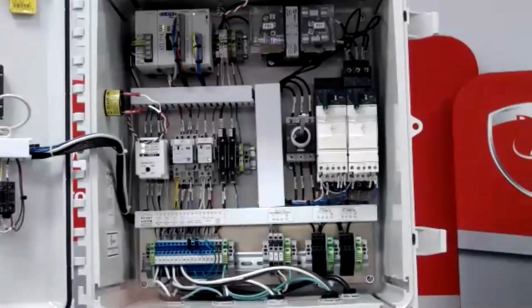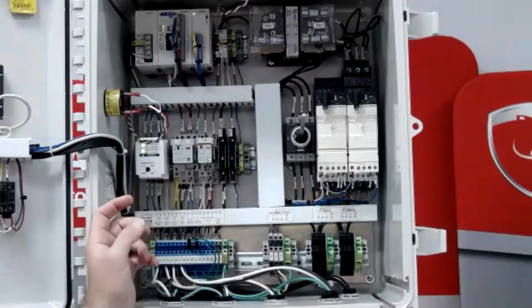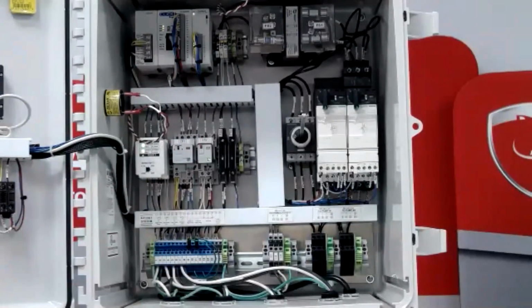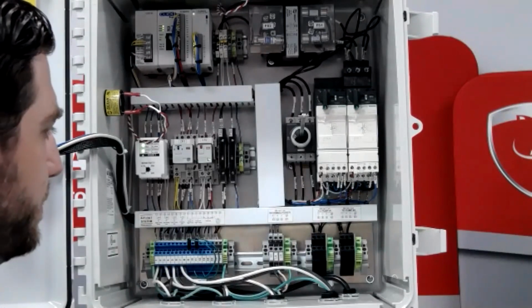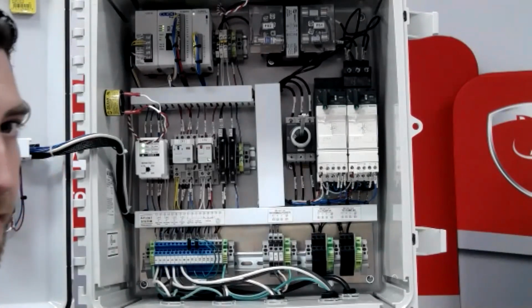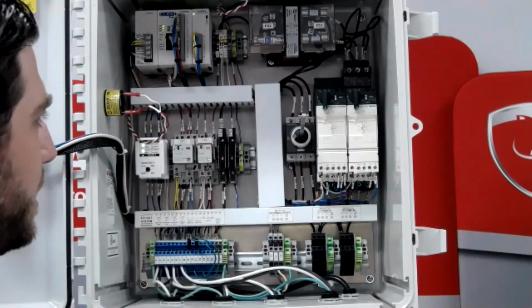You can see we have the PLC there, and we have the backup relay. So if we do get our high-level alarm on this control panel, it's going to bypass the PLC and bring in both motors. So it's a backup, a kind of fail-safe design, in case all of our float switches don't come in.